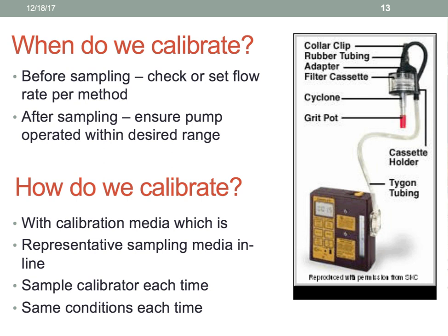Here is another example of a sampling train, not a calibration train. You have your pump connected to your inlet, here's your Tygon tubing connected to the inlet of your cyclone. The air is pulled in here and flows gently to the cyclone. It spins around, and the particles that are too heavy fall down into the grit pot. Those that are light enough attach themselves to our filter.